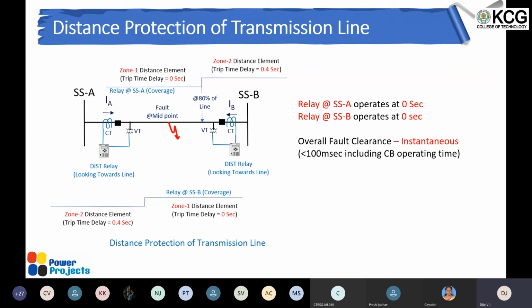The other point is the distance protection. I'll just give a brief of the distance protection, how the setting will be adopted by the protection engineer. Basically, the relay will be kept at both ends, and each relay will be seeing the fault in the forward direction. Based on the setting, generally the first zone, which we call zone 1, will be set to cover up to 80% of the line. Generally it does not go beyond that. So up to 80% of the line is the first zone of protection, and the impedance setting will be given in the relay accordingly.